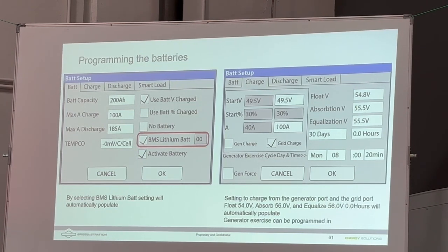All right, this capacity and max charge rate and max discharge rate allows you to set a global limit. Now, the battery itself will set its own limit. The capacity should automatically be filled out here. But whatever limit you set here for the max charge rate, if the battery is requesting a different charge rate, it will take whatever the minimum is. So for instance, there might be some reason that you want to limit the overall rate at which your batteries charge. The batteries have a default rate that's built into them, which is, I think, a 0.7 C rate. If you limit it more here, it will take the smaller value of the two.